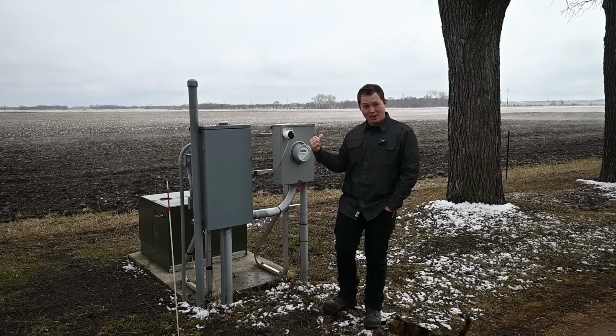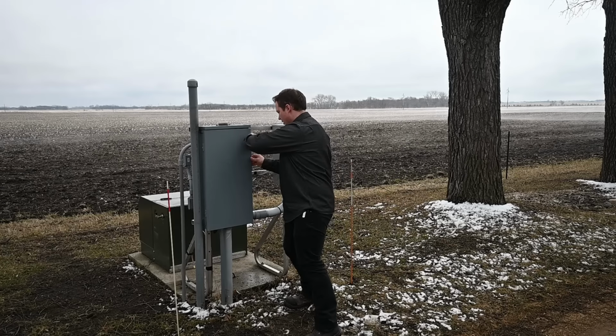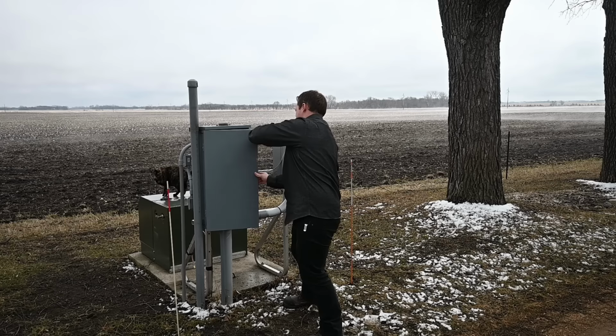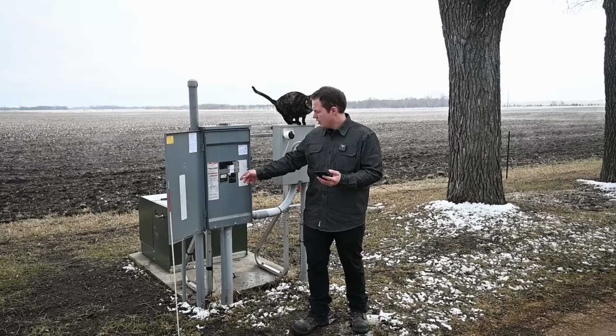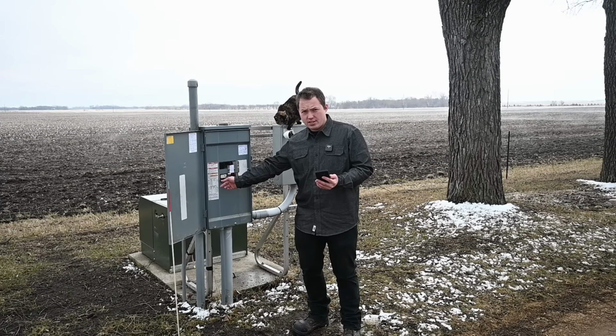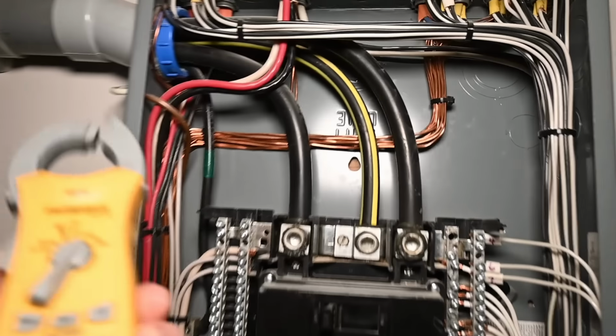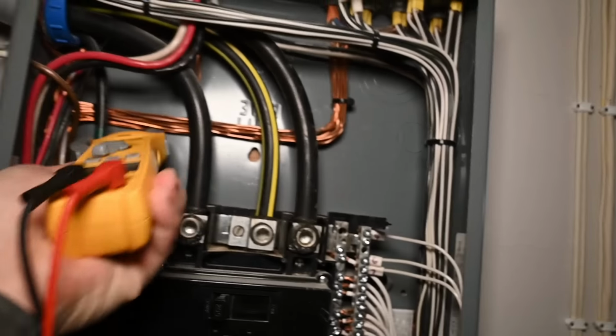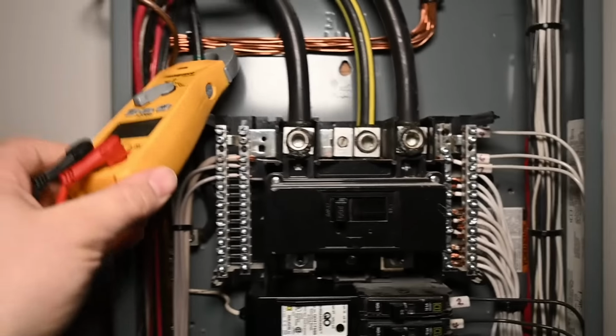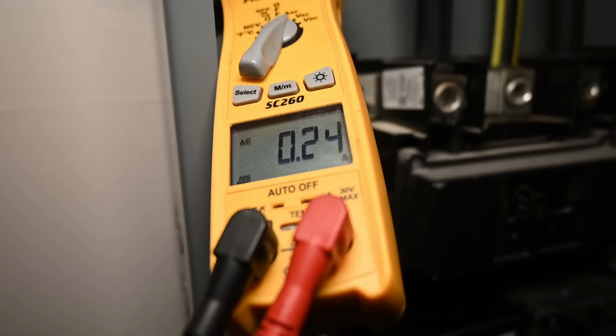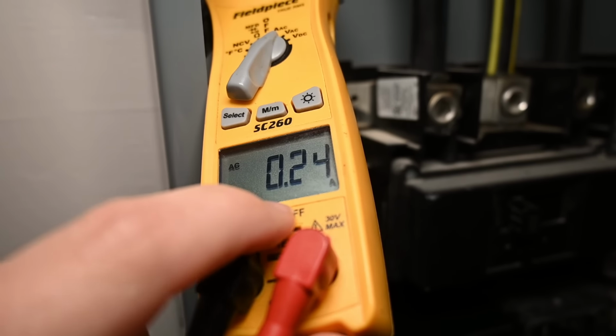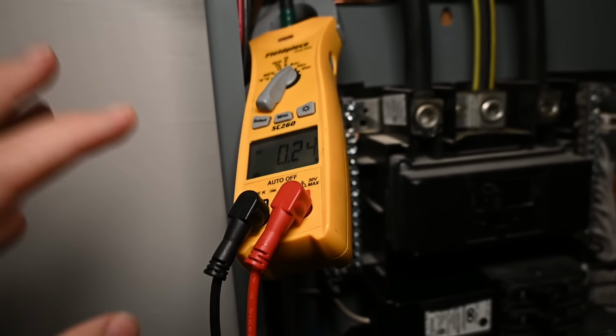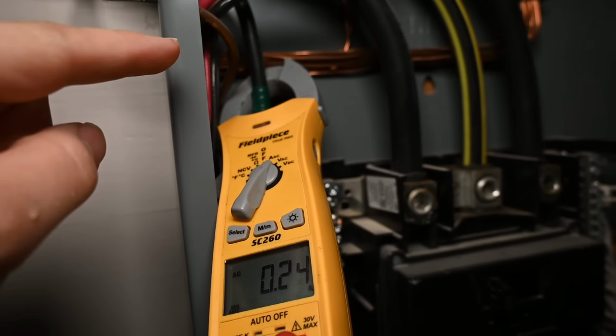All right, here we are out at the first panel in the yard. I'm gonna open this up and shut off all of the circuits here, to find out if that took care of it. So inside our panel now, there's no power turned on at all. And oh my word, there's still 0.24 amps running through that EGC.